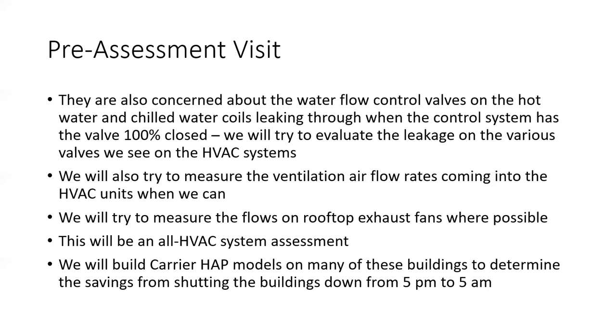So this is going to be an all HVAC system assessment. We'll also, you know, a long-term goal when we come back will be to build Carrier Hourly Analysis Program models. That's modeling software we have from Carrier to predict what the energy savings would be if we went from 24/7 operation, which they're in now, to basically 24 hours a day, 5 days a week, 12 hours. So they would shut these systems down like they used to from, say, 5 p.m. to 5 a.m. So we'll try to use that software to make some projections on that. So there you have it. That's the end of that.